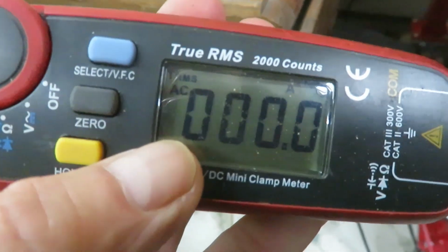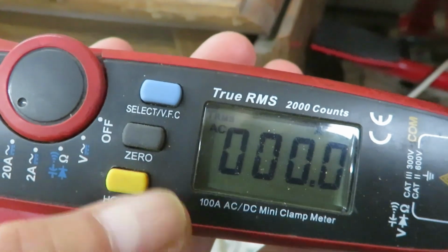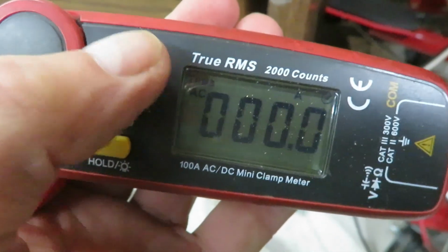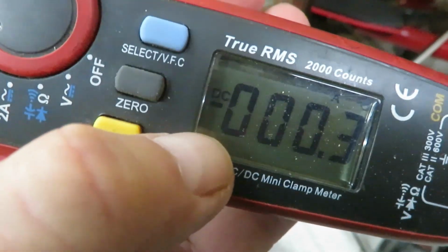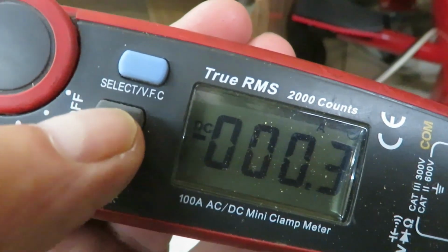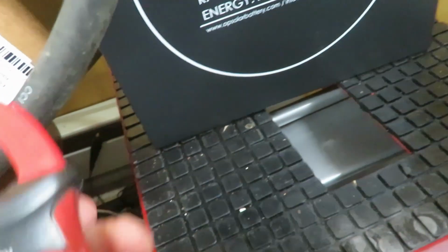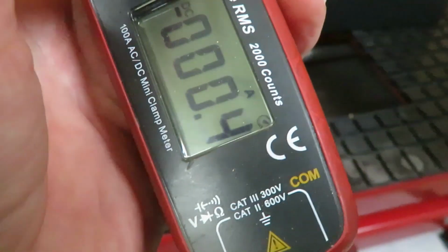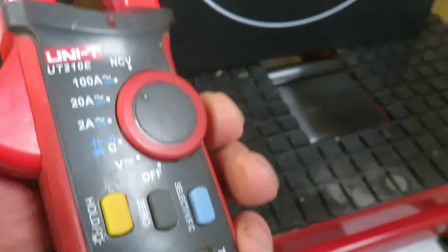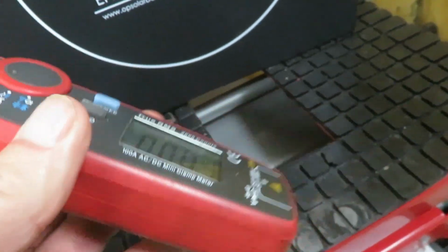On this meter you can see it's set to AC - it's an AC-DC clamp meter, but you need to select DC. There, now it's in DC mode. When you're in DC there's a plus and a minus, so you want this going to the positive side, which will be the battery. First you have to zero it out - you hold this here and press the zero button, so that zeroes it out on DC. You don't have to do that on AC. It's just big enough to go on here, so I'll put a load on there and see what happens.